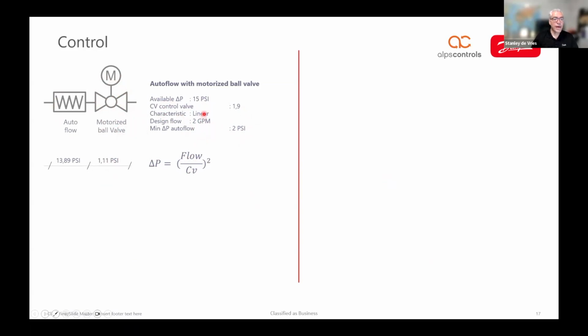So that means that since we have 15 available, the rest of the pressure drop actually falls on the autoflow. Because that is its function, right? It maintains the flow. And if the flow wants to be higher, then it will increase the pressure drop, or basically close, to make sure that it doesn't have an overflow. So far, so good. Great solution. And for balance, at full load, your system will run perfect. The problem with that is that full load is a situation that doesn't really happen that much.